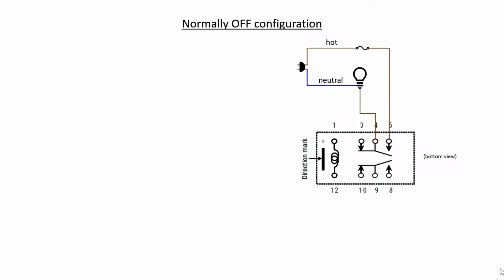We're going to be switching off a lamp in our example relay circuit, and we're going to be using the normally off configuration. One thing that's important to keep in mind is that you always want to install a relay, or any switch for that matter, on the hot side of a circuit. You don't want to switch the neutral side of a circuit on and off.